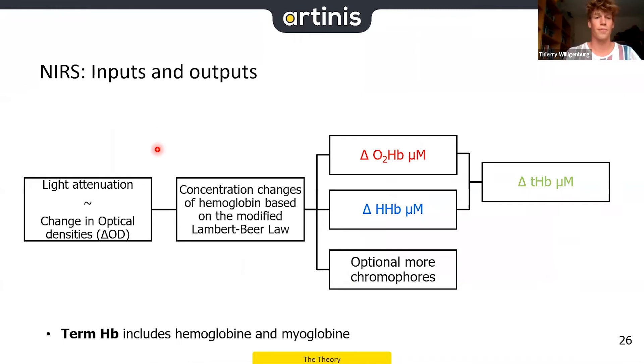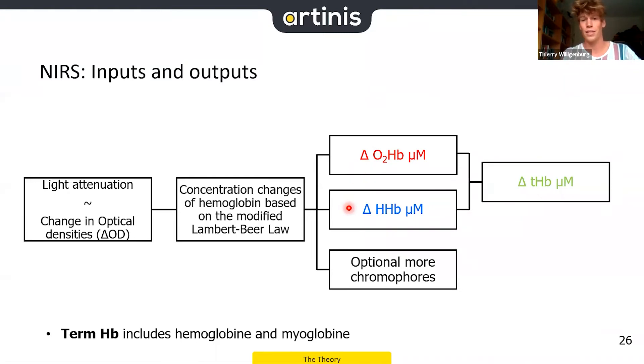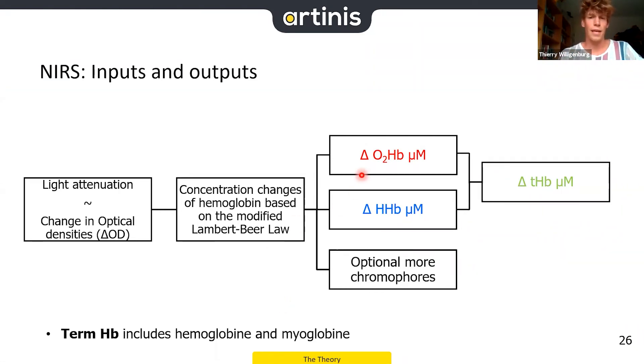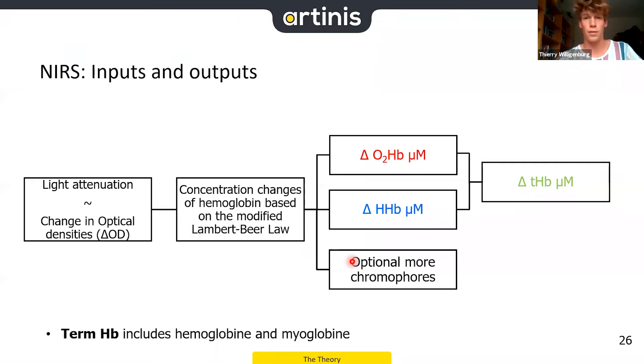With NIRS we measure light attenuation, and based on the modified Beer-Lambert law we can quantify changes in oxyhemoglobin and deoxyhemoglobin. Adding these gives total hemoglobin. Note these are changes relative to a baseline. Also noteworthy: we cannot distinguish between hemoglobin and myoglobin — myoglobin takes approximately 5–10% of the signal, but during exercise your changes happen in hemoglobin while myoglobin remains stable. At 850nm we quantify oxyhemoglobin; at 760nm, deoxyhemoglobin. Optionally, other chromophores such as cytochrome oxidase can also be measured.